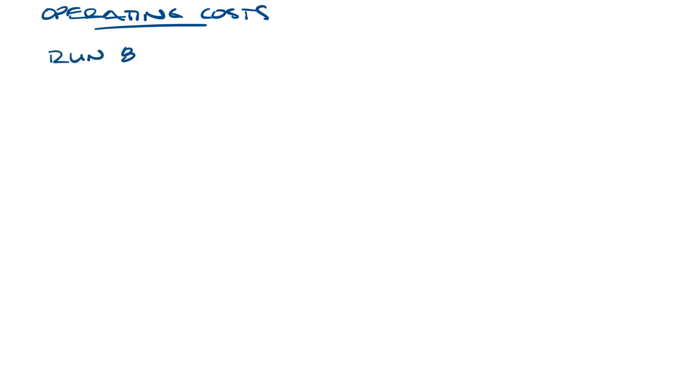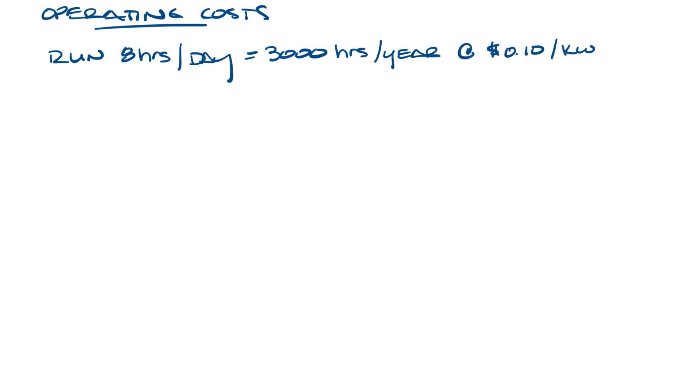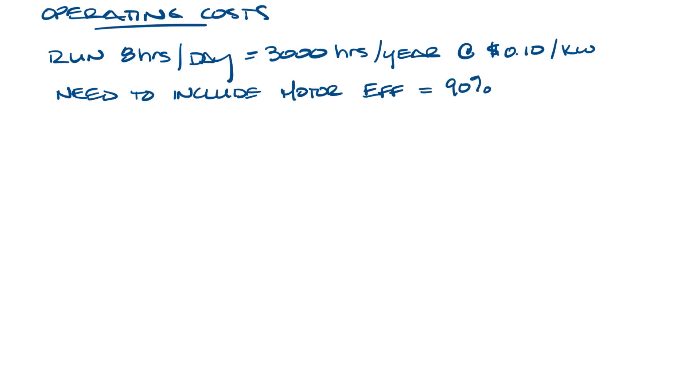So let's say all of these will run for eight hours a day every day, so that's 3,000 operating hours a year, and let's say it's at a cost at 10 cents per kilowatt. The pump efficiency number doesn't include the motor efficiency, so let's say they all have the same 90% efficient motor.